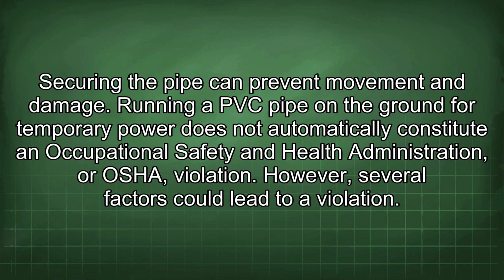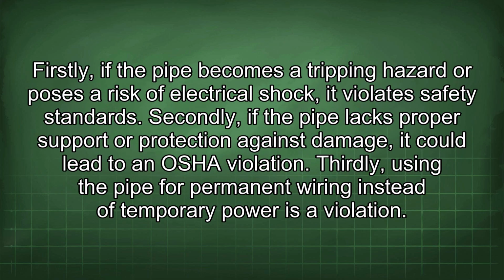Running a PVC pipe on the ground for temporary power does not automatically constitute an Occupational Safety and Health Administration, or OSHA, violation. However, several factors could lead to a violation. Firstly, if the pipe becomes a tripping hazard or poses a risk of electrical shock, it violates safety standards. Secondly, if the pipe lacks proper support or protection against damage, it could lead to an OSHA violation. Thirdly, using the pipe for permanent wiring instead of temporary power is a violation.